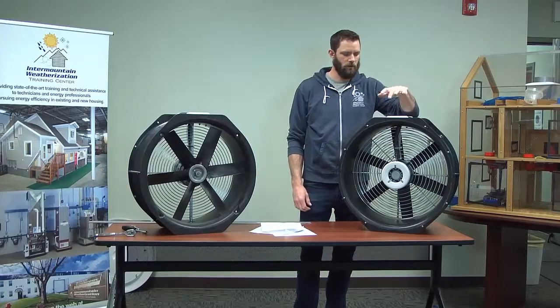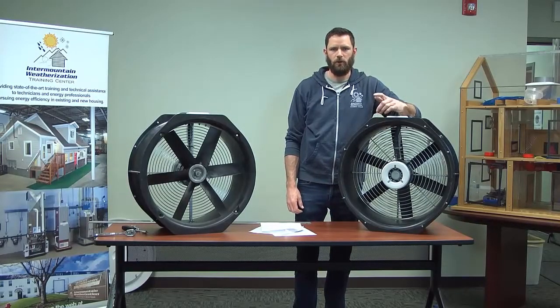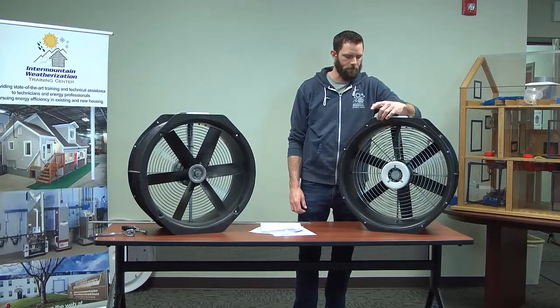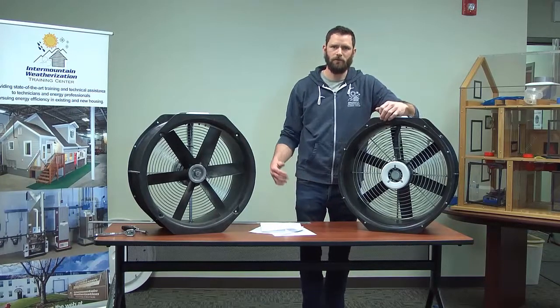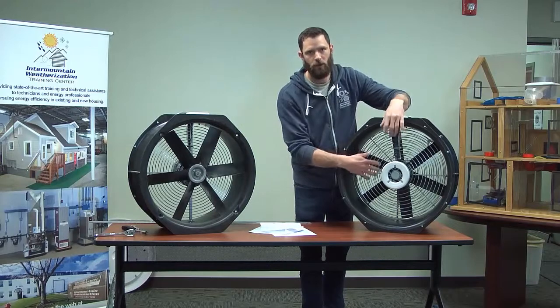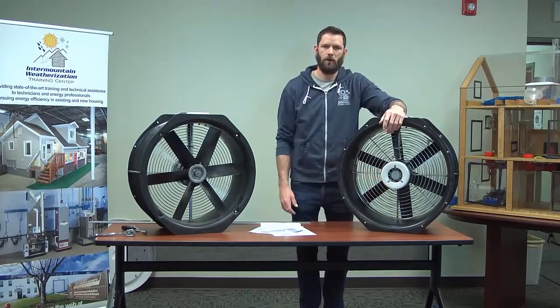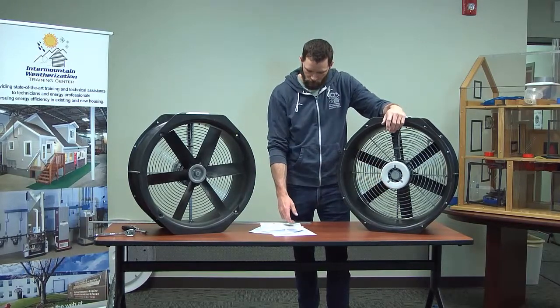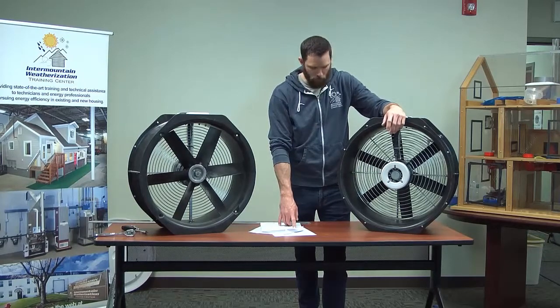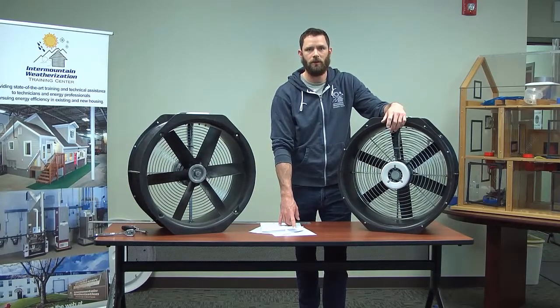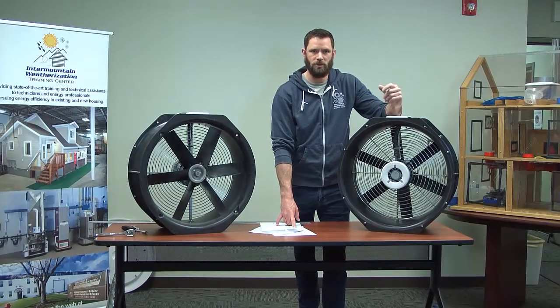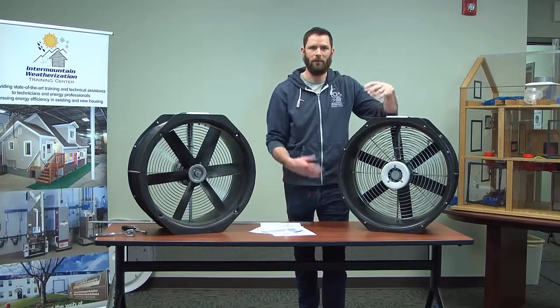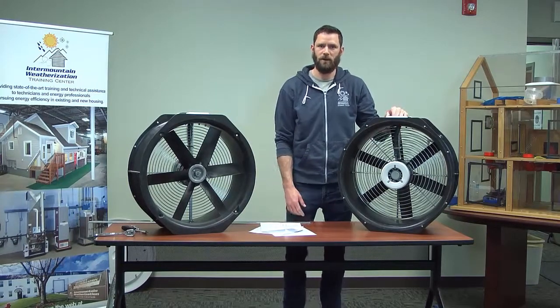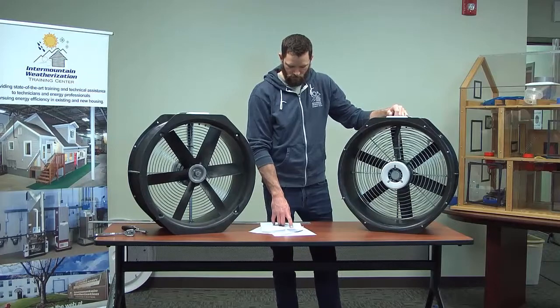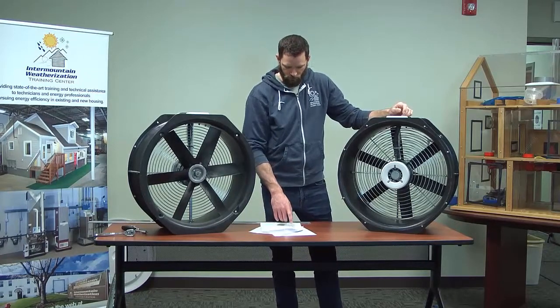If you're going to be running the blower door for long periods of time, like when you're doing air sealing, you want to make sure there's a flow ring on it, because that helps guide that cool air onto the blower motor and will help keep it cooled down. If the motor gets too hot, it will shut down, and so that could be an indication if your blower door keeps shutting down on you. You may not be getting enough airflow, so you may want to inspect the motor and see if it's not getting enough airflow on it.